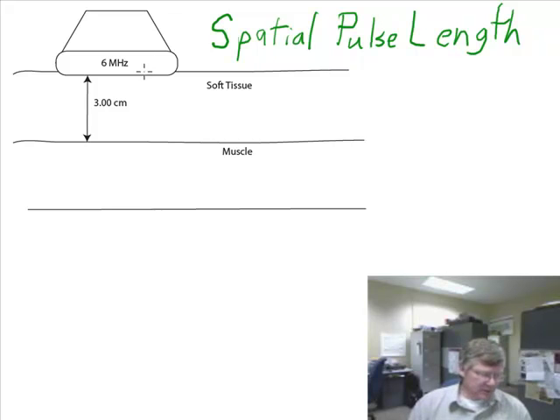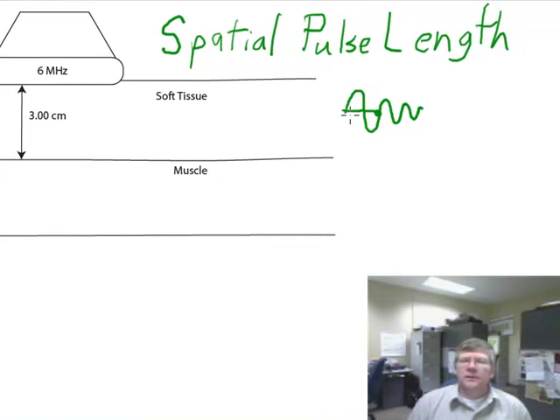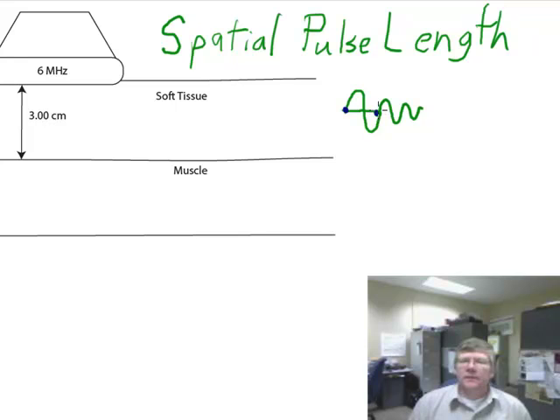When a transducer emits a pulse, it doesn't just send out a single wavelength. Usually it oscillates a few times, and the oscillation decreases until it gradually fades out. Looking at the number of wavelengths generated, we might have one full wavelength, then another, and then another. One, two, three full wavelengths before the pulse dies out completely. This is the pulse generated by the ultrasound transducer.